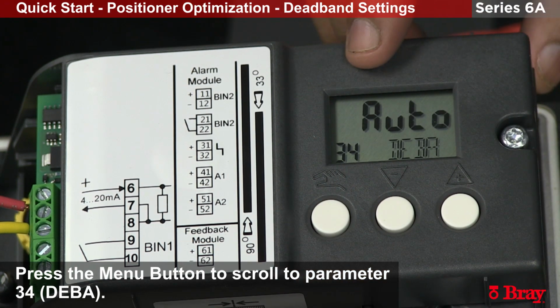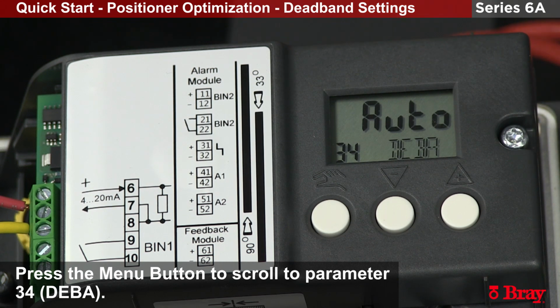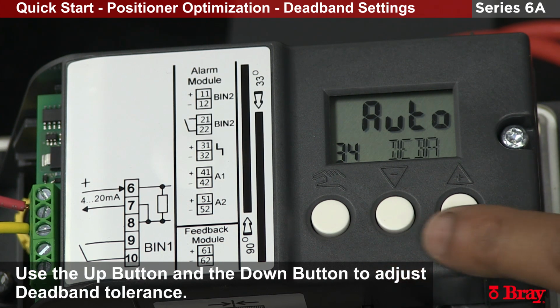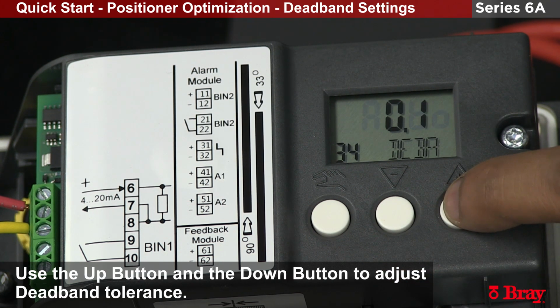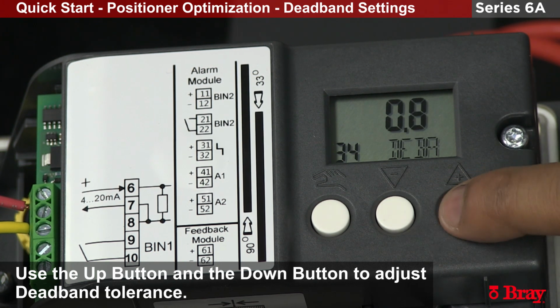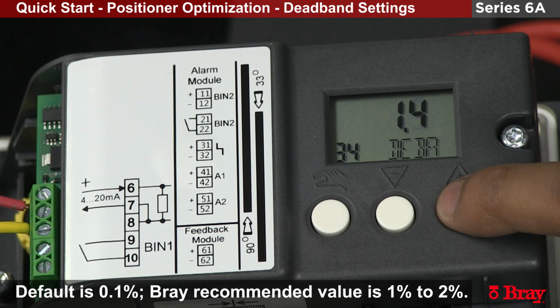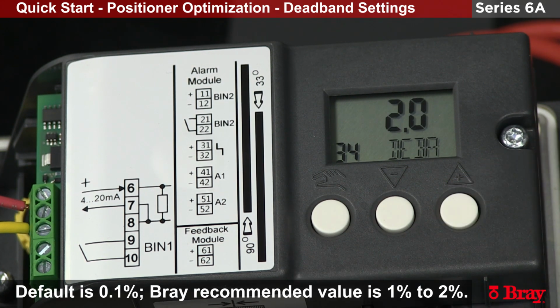From the factory, it will be set as auto, which is telling the 6A to achieve a 0.1% accuracy. We can adjust this by using the plus and minus buttons to change this setting. We can increase the tolerance to up to whatever percent is applicable to your application. In this example, we'll set it to 2.